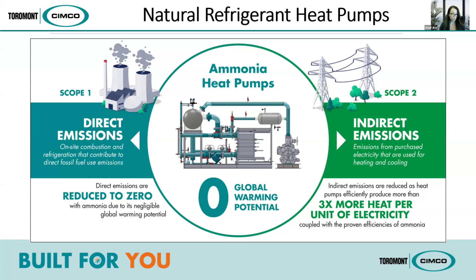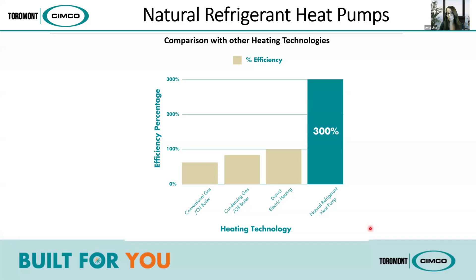This is a slide of efficiency ratings compared to your heating technology. The one to the right is your natural refrigerant heat pump, and then you have electric heating to the left, between 99% and 100%. You have the condensing oil boiler to the left of that, and then your conventional oil boiler to the left of that. With natural refrigerant heat pumps, you have an efficiency of about 300% to 400%, so you're utilizing less electricity to run it - about 25 to 30% - so it becomes a very efficient clean energy source, especially if you have renewables to integrate into the picture.